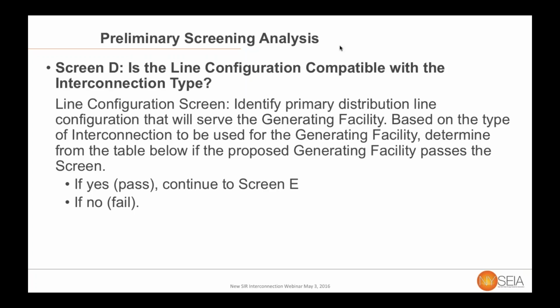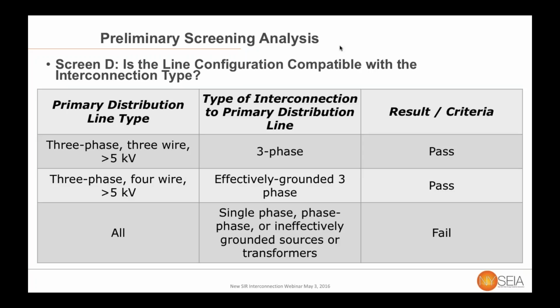Screen D, it asks, is the line configuration compatible with your interconnection type? So this is going to show a table here, and it simply asks, is your proposed method of interconnection consistent with the existing distribution system? So this table is included in the SIR. So it has the three options, so three-phase, three-wire systems over 5 kV. Any three-phase type of interconnection is acceptable and you can pass.